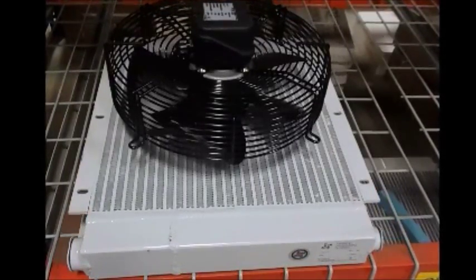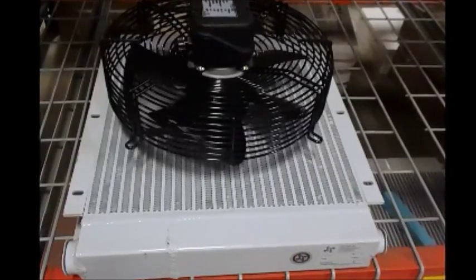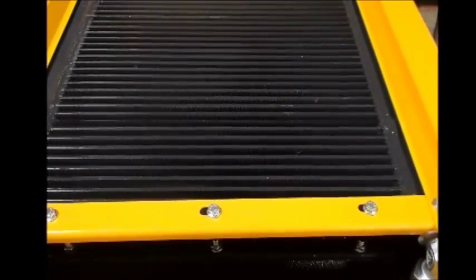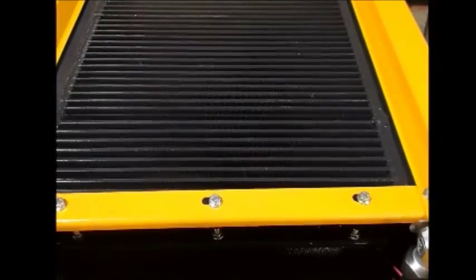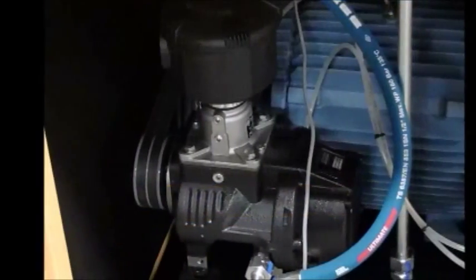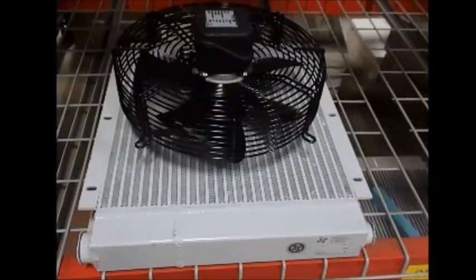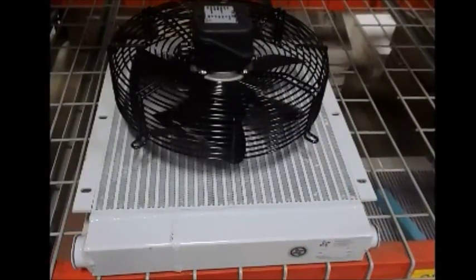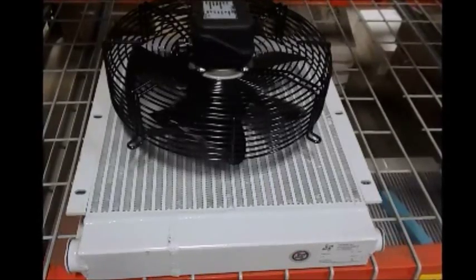The oil cooler portion of the radiator is the life of the rotary screw compressor pump. While under the compression state, the hot oil is transferred from the compressor pump through the radiator where heat is dissipated. The cooled oil is then returned to the pump for another heat transfer cycle. The oil cools the compressor pump internally, allowing up to 100% duty cycle.